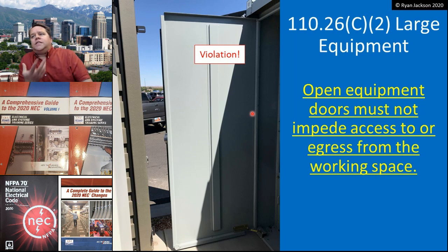And I think in many applications, this change really increases worker safety and is a great change in most applications. In the photograph here, I think this is a prime example of this new rule working extremely well. It says, and let's make sure we're on the same page, we're still talking about large equipment, so 6 foot wide, 1200 amps or more: open equipment doors must not impede access to or egress from the working space. Okay, so here I have a switchboard.